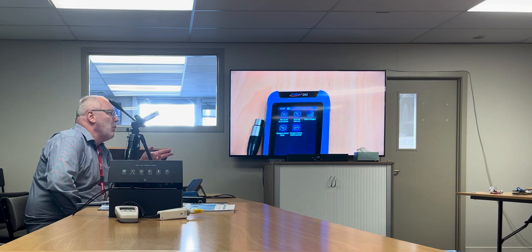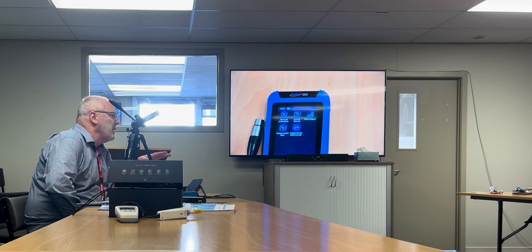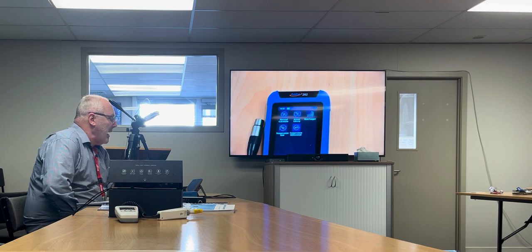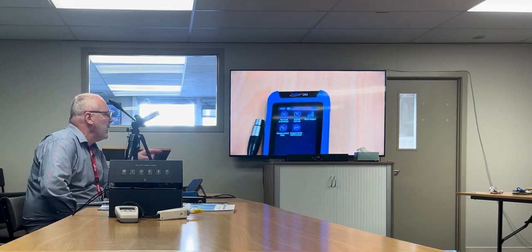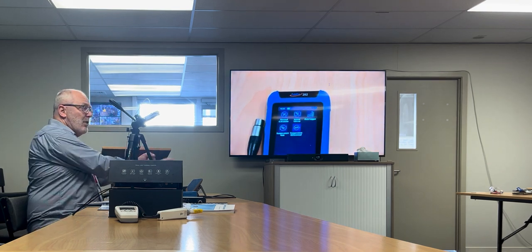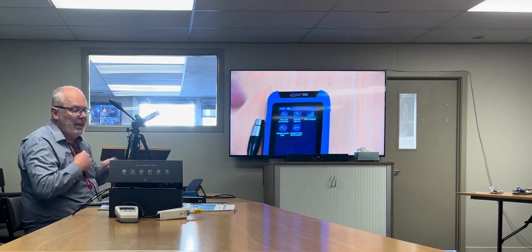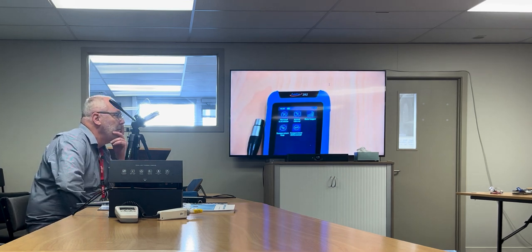You're quite right, that's a standard calibration as described in their manual. You could lock a single smart probe to channel one, say with a password, so if you've got a junior doing it, channel one is always going to be that smart probe, locked with a password, and then compare it against the other probes under test. You've exactly described how you would do it.